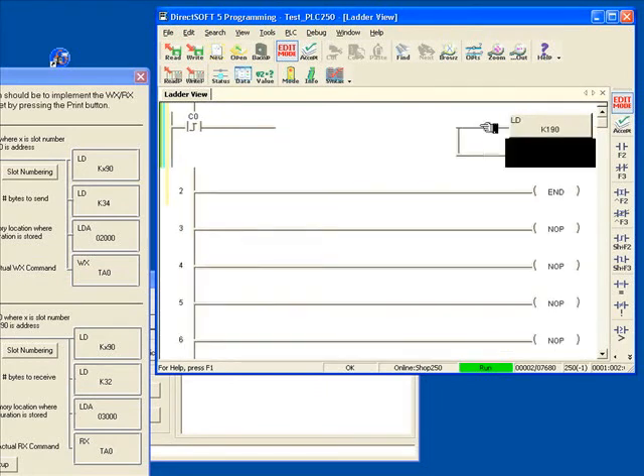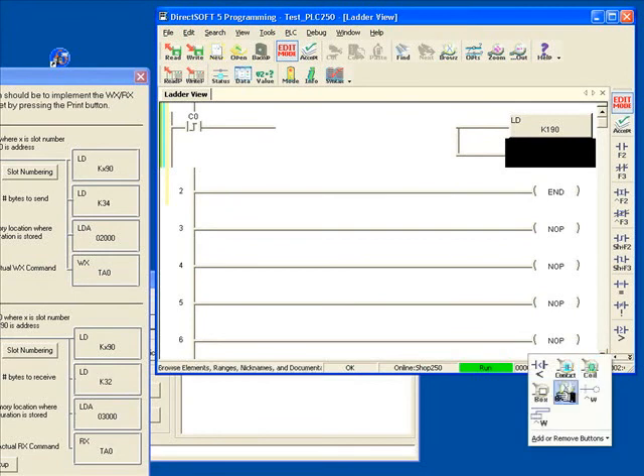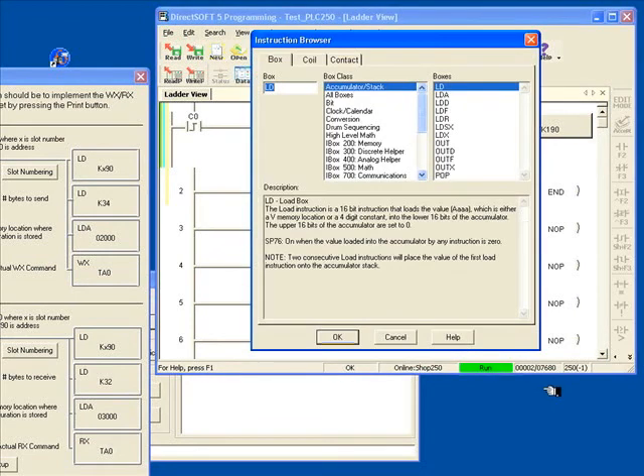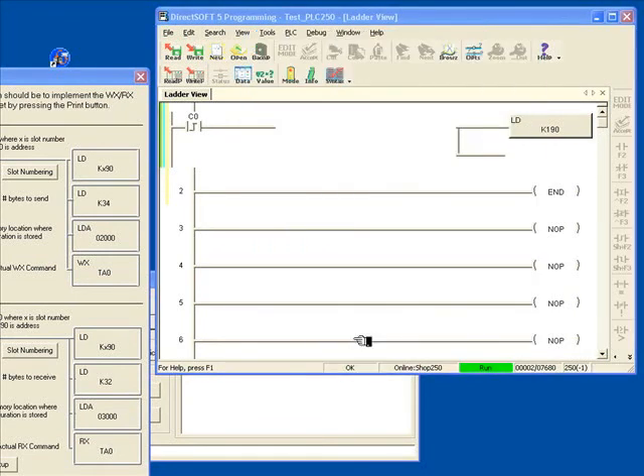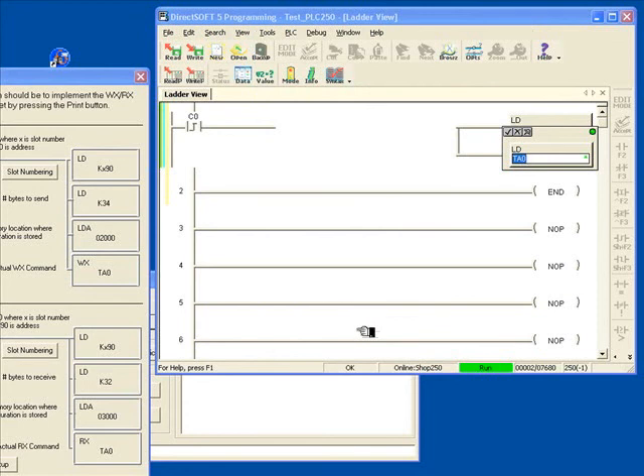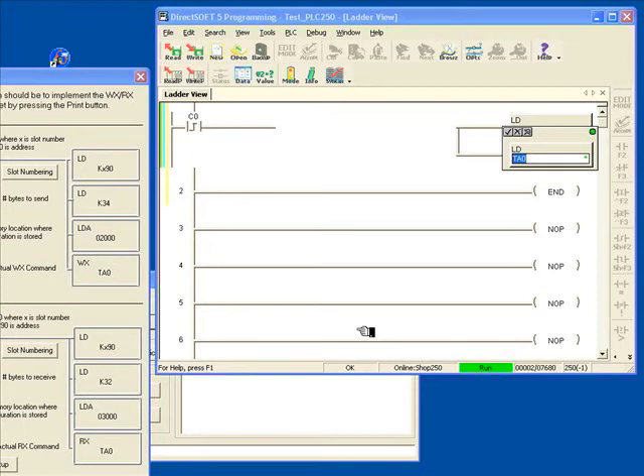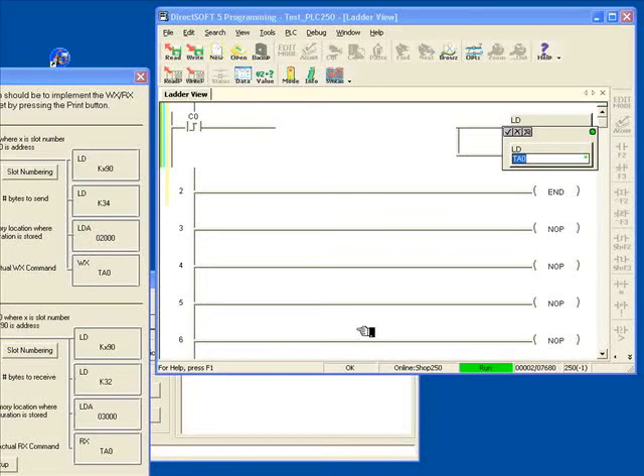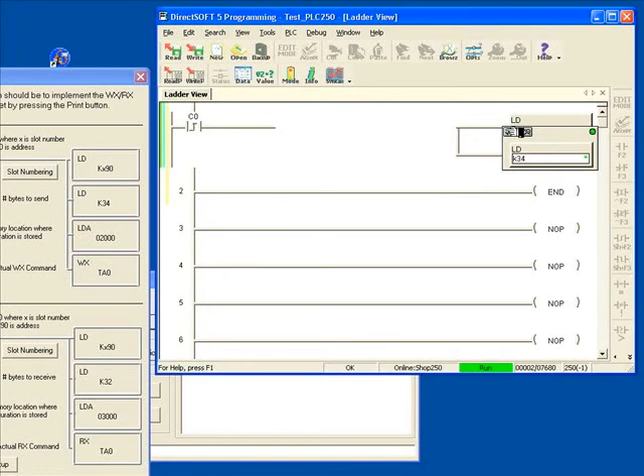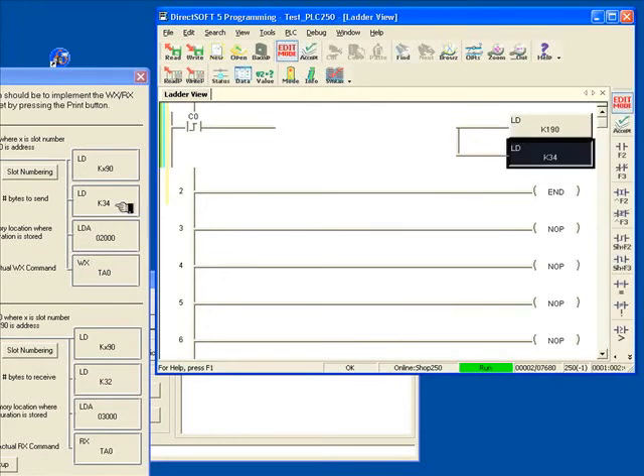And we'll go ahead and put another block down here, and we'll do a load. And this is going to be how many bytes of data that we're going to send. If we're going to send just one word, it's going to be two bytes, but there's some setup words you have to send. So it would be 32 plus the number of bytes. So in this case, we're going to send just one word, so it's going to be a load K34. So we'll do a K34. Now if you were to send two words, it would be a load K36. And you can see here that DirectSOFT will actually show you what it is based on how many data values that you've selected.